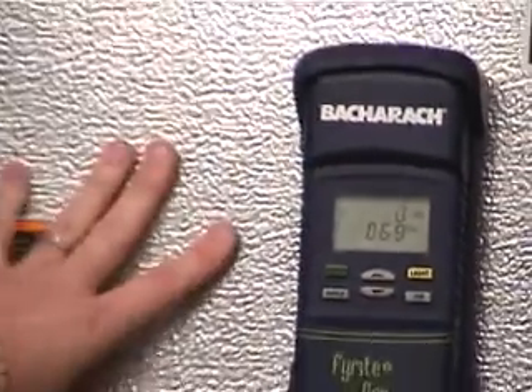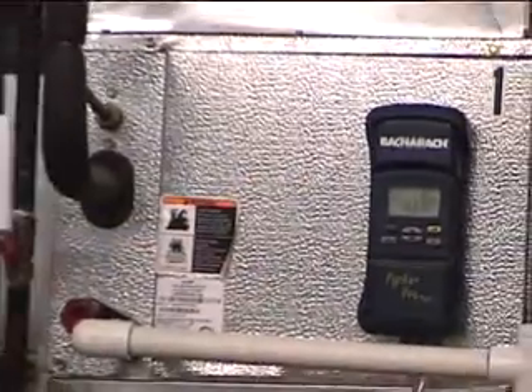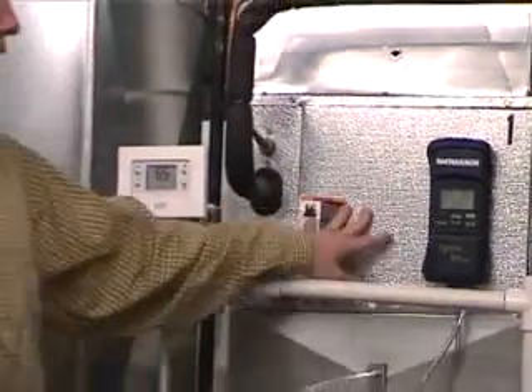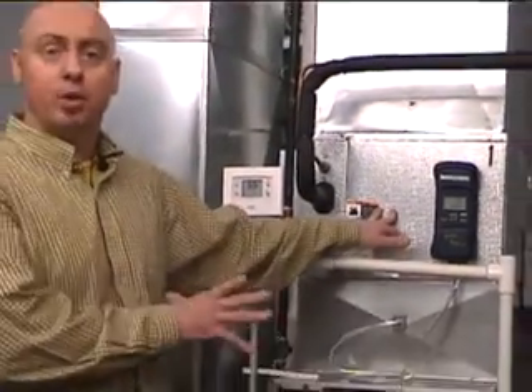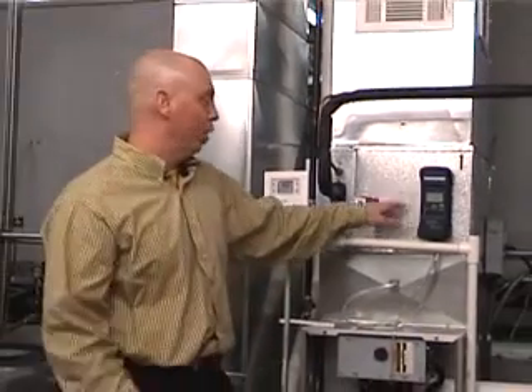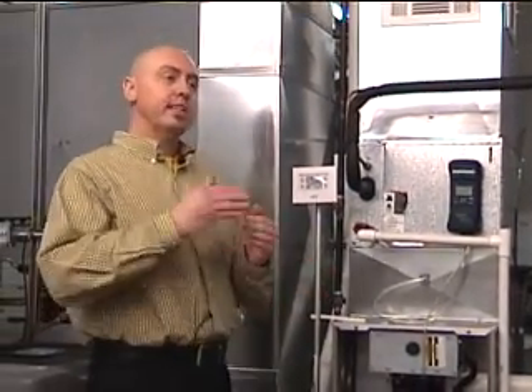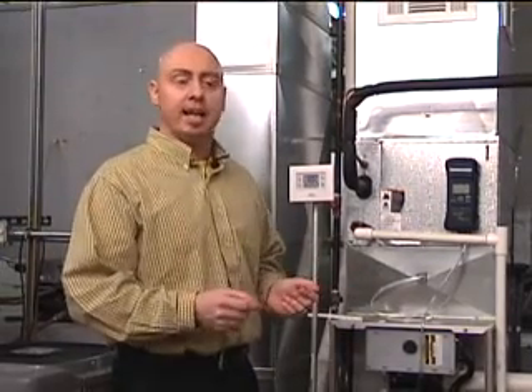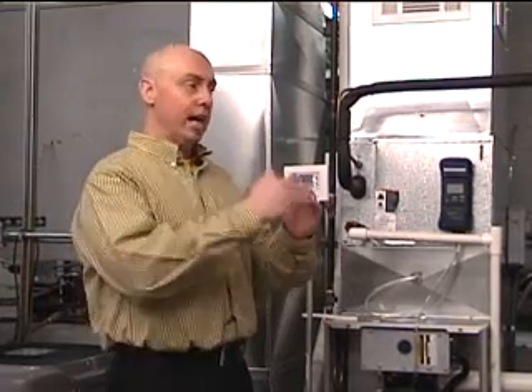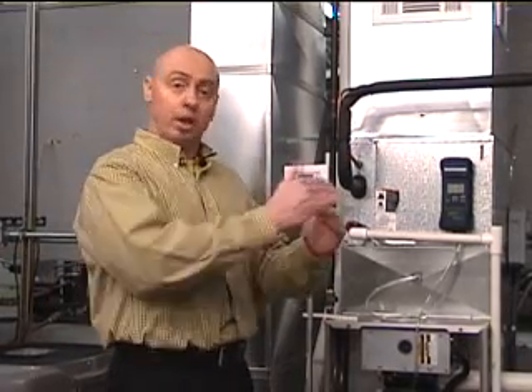Now when you have a piece of equipment like this, keeping in mind that 0.5 is a cooling number, I'm running on continuous fan, which happens to be on this piece of equipment the low heating speed. So when I went to cooling, I could very easily be running at 1 inch of static pressure. And as soon as that static pressure goes up, airflow is compromised. Think of it in the sense that airflow is inversely proportional to static pressure. The higher the static pressure, the less airflow. The lower the static pressure, the more airflow.